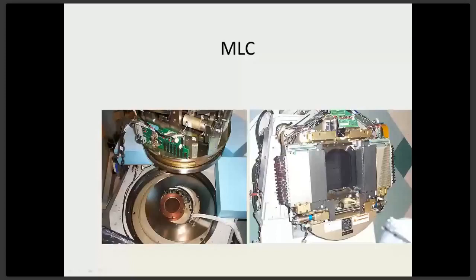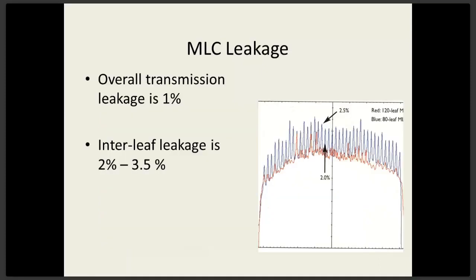Here's a quick picture that shows you what the ion chamber looks like. And this is the ion chamber assembly right here, deep in the head of the machine. And of course, this is the multi-leaf collimator that we're all familiar with. These are the vanes of the multi-leaf collimator. Sometimes people want to know about multi-leaf collimator leakage. Interleaf leakage is about 2%. And overall transmission is less than 1%, which is way better than Cerrobend blocks.